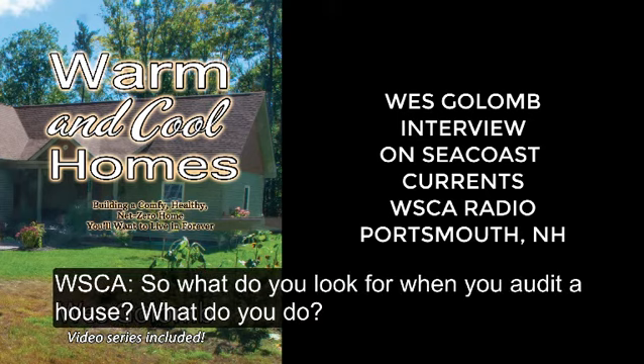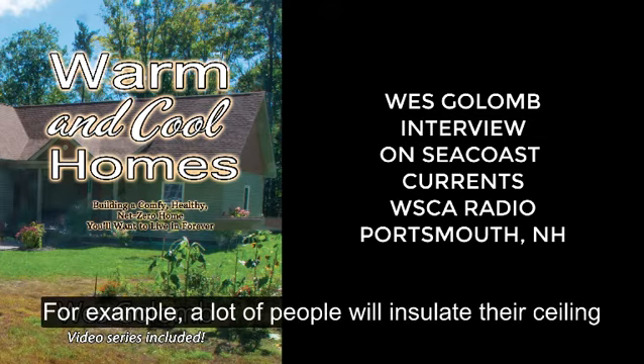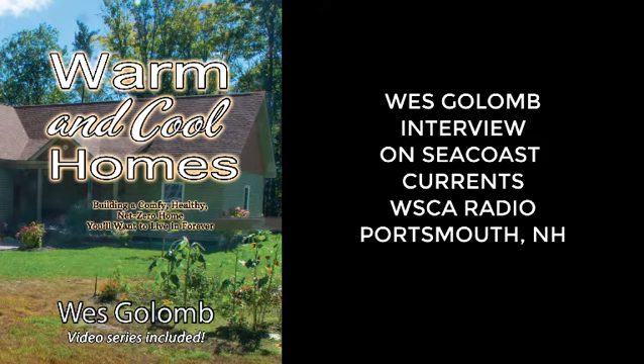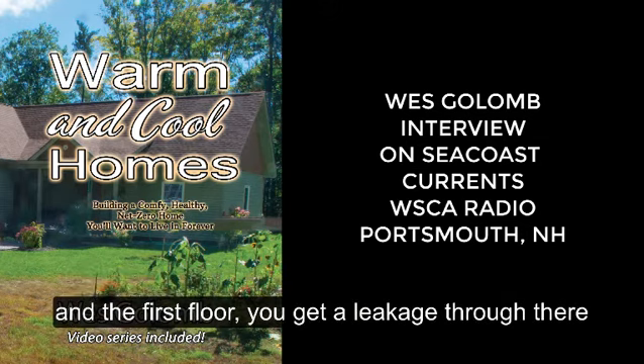What do you do? Well, the first thing you do is you look to see what the envelope actually is. Where is the envelope? For example, a lot of people will insulate the ceiling of the basement when, in fact, the natural envelope of the house is actually the basement walls. And you've got a door that opens and lots of holes between the basement and the first floor. You get a lot of leakage through there.